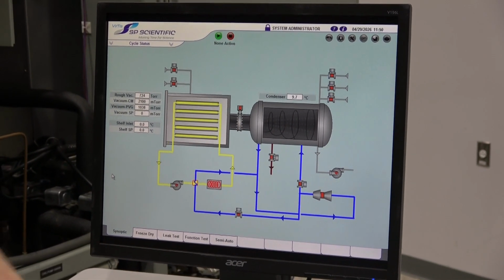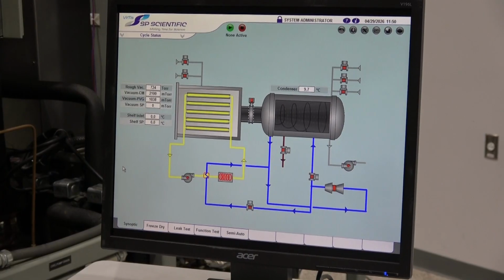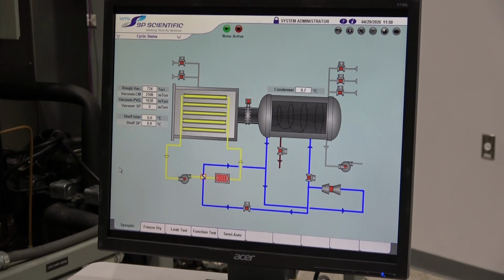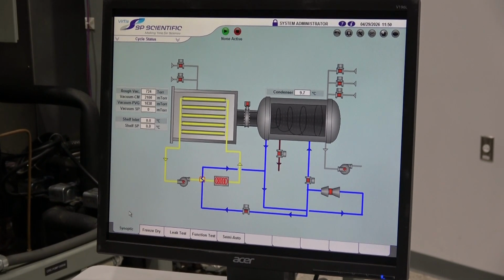It does have the isolation valve, so that's really nice because you can do your pressure rise test for moisture levels to advance to the next system whenever you're doing your recipes.